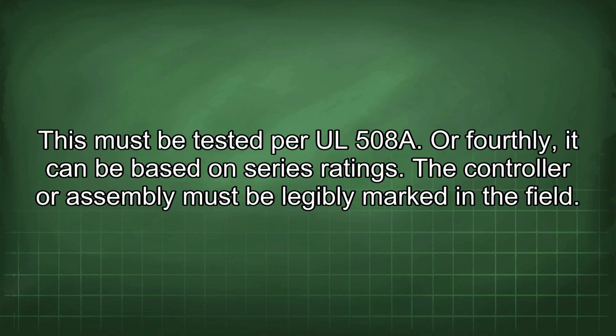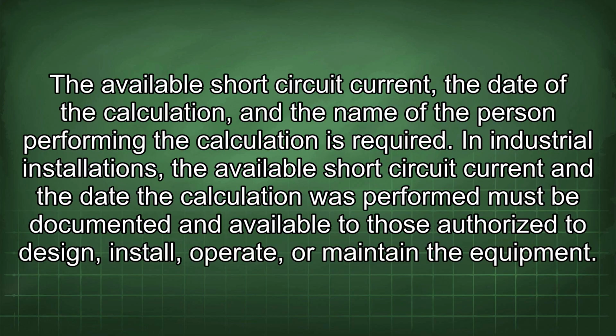The controller or assembly must be legibly marked in the field. The available short-circuit current, the date of the calculation, and the name of the person performing the calculation are required. In industrial installations, the available short-circuit current and the date the calculation was performed must be documented and available to those authorized to design, install, operate, or maintain the equipment.